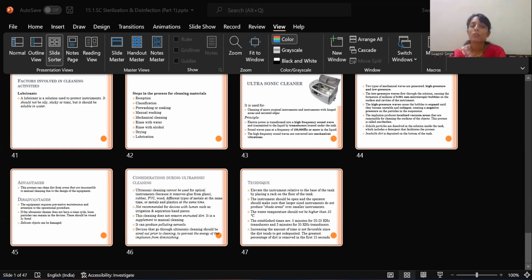Now, the risk for non-sterility chiefly resides in the residual number of microorganisms, which further depends on the initial concentration with respect to the volume or mass of the articles that have been sterilized, in the volume or surface of the articles that will be sterilized, and the effectiveness of the sterilization, which is expressed in terms of the number of decimal reductions. After sterilization, the average number of microorganisms is referred to as R, which is the probability that an article is non-sterile, or the risk of non-sterility of the article. It is the product of C0 into V or S into 10 to the power of minus D, where the European and American pharmacopoeias have set 10 to the power of minus 6 as the maximum limit for the probability of non-sterility.